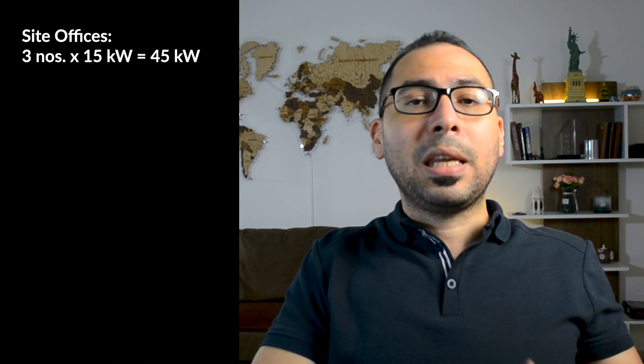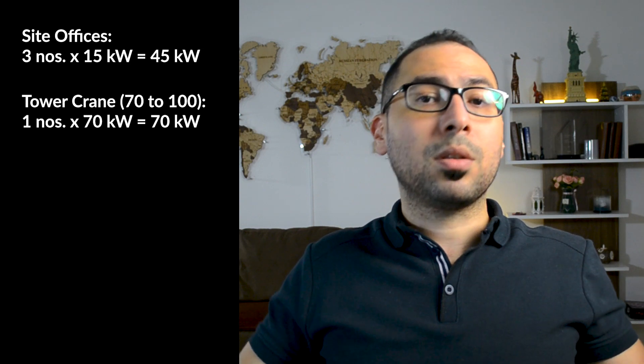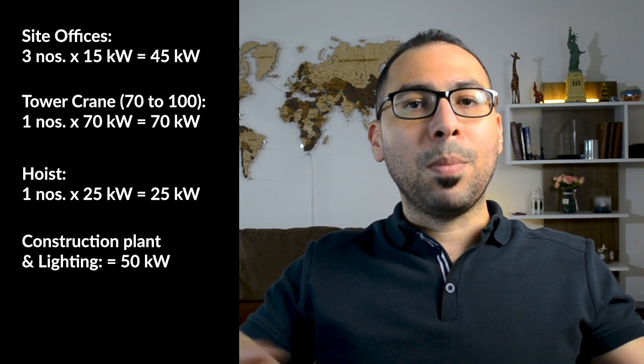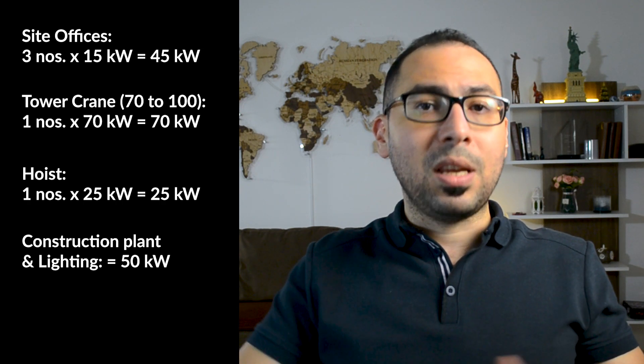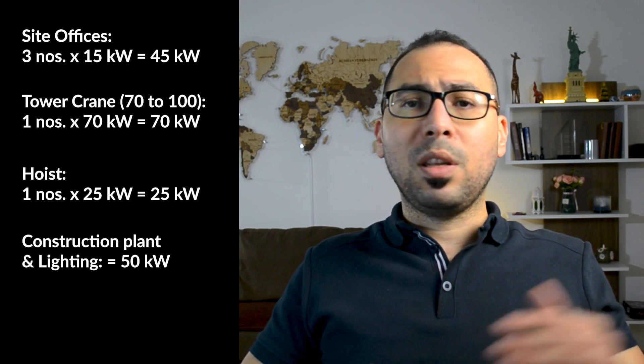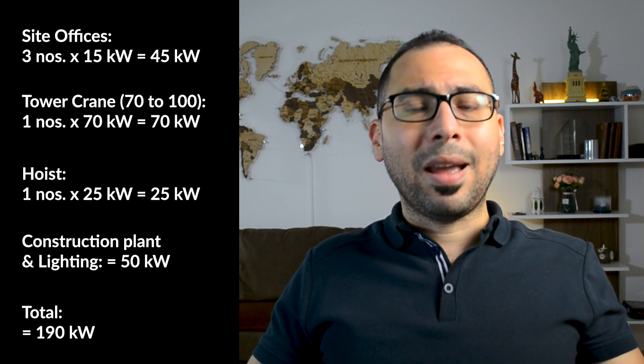For example, one porta cabin site office with two AC units, six or seven lighting points, and five or six power points might require 15 kilowatts. Three porta cabins would be 45 kilowatts. A tower crane might require 75 kilowatts, a hoist around 20 to 25 kilowatts, and construction plant and tools perhaps 50 kilowatts more. So the total power requirements come to around 190 kilowatts.